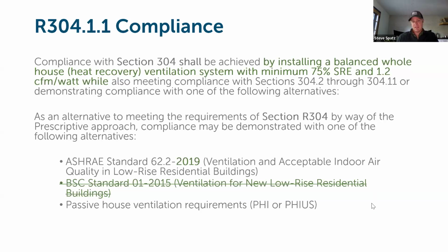There are bases of design for sizing mechanical equipment and how much ventilation air is required specific to the building that's being built, just like you would be doing a design load calculation for a heating or cooling system, and specifically designing to that building's need for what type of mechanical heating or cooling system is required. The ASHRAE 62.2 standard exists as the industry standard of design for minimum ventilation rates for single family construction. The Passive House Institute also has ventilation standards that they have developed, which are considered equivalent to the ASHRAE approach to model your CFM needs. But the ASHRAE approach has been pretty much the common method to use in our market.